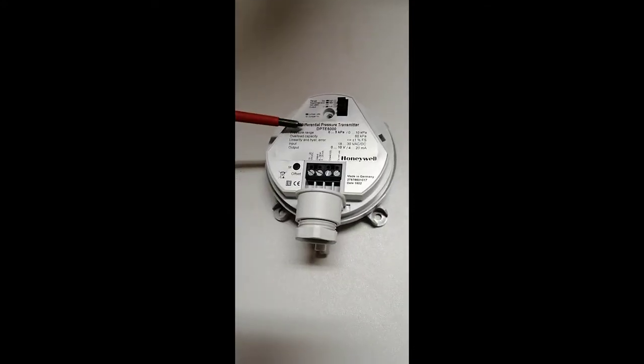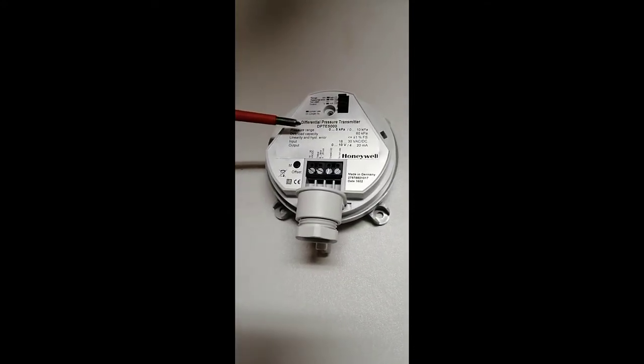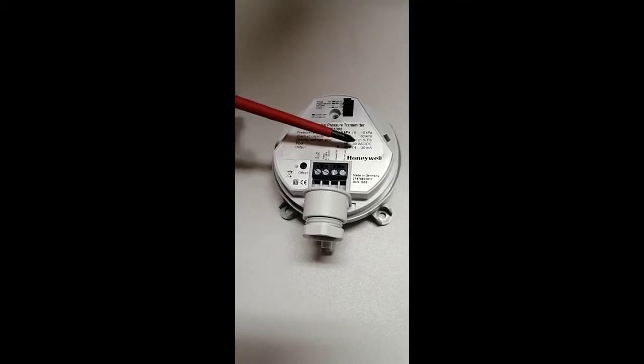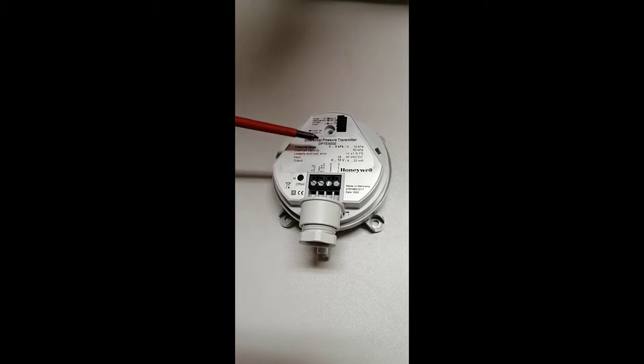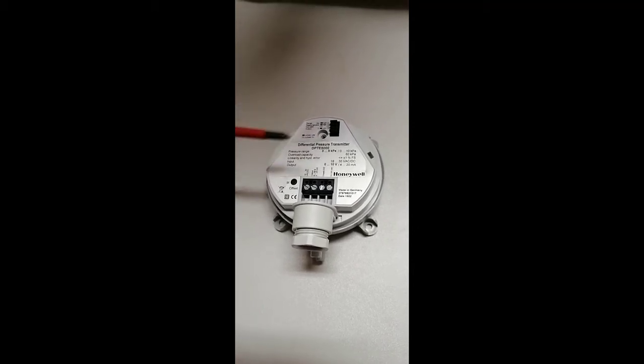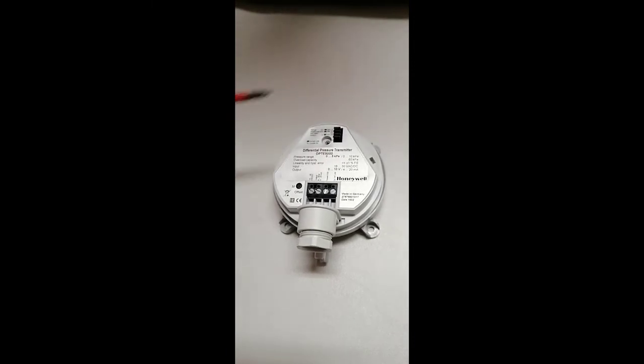It is an active device which needs a power supply for its functioning. It provides us a 0 to 10 volt signal or 4 to 20 milliampere signal, and its range is from 0 to 5 kilopascal, or we can also select from 0 to 10 kilopascal.